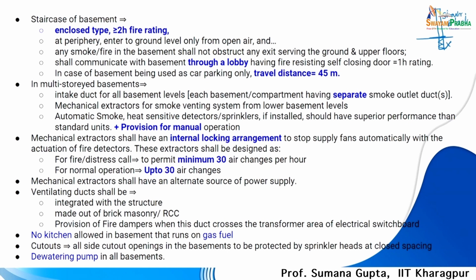Internal mechanical extractors shall have an internal locking arrangement to stop supply fans automatically within the basement upon actuation of the fire detectors. These extractors shall be designed for distress calls. For normal operation it is 30 air changes. Ventilation ducts shall be integrated with the structure, made out of brick masonry or RCC, with a fire rating of 2 hours or more. So, the basement staircase is expected to be at the periphery, and the fire staircase should not go down to the basement.